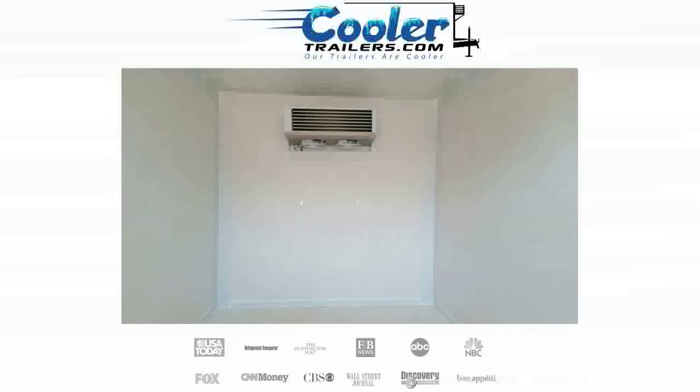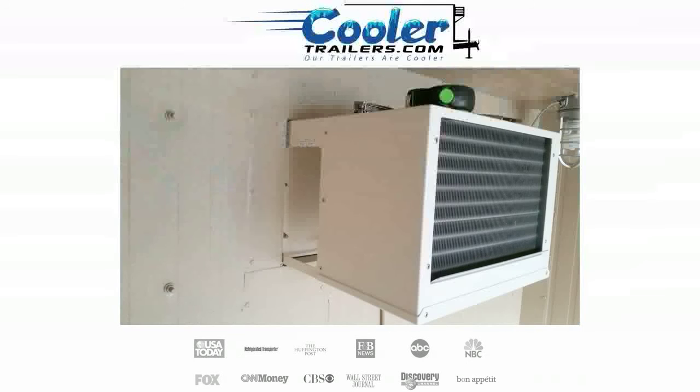Things like moist hot days and door openings can speed up this process, but at some point you're going to need to defrost the ice accumulation on that coil. There definitely are a few ways to go about it. The least effective is someone telling you to just shut the unit off for an hour to an hour and a half, with uncertainty that it's defrosted.